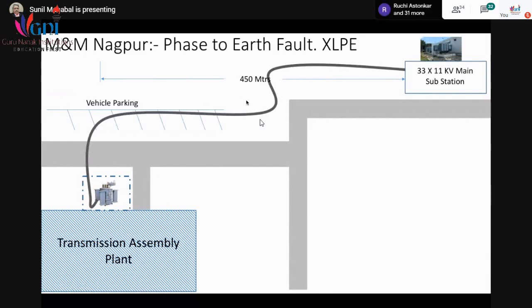When we connected it, we installed the RMU on Sunday when the factory was closed. We did the installation during the day, and in the evening we wanted to charge the circuit so that next day morning at 7 a.m. the plant starts and the production starts. So we charged the cable with 11 kV, and as soon as we charged it, it got punctured and there was a phase to earth fault. Then it was a very big question mark because it was already 6 p.m. in the evening.